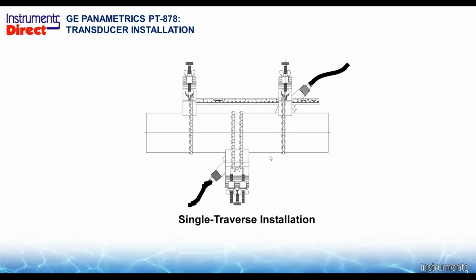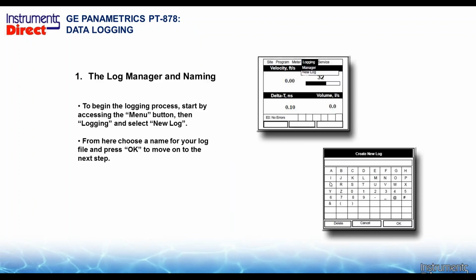You may not have to go to this plane. You need to go up and down this plane to find the sweet spot. So the single traverse is more powerful, but more difficult to do. And so you usually reserve it to larger pipe size applications. Now, the device has a logger, so if you want to leave it there for a while to collect data, I don't remember, like 100,000 data points here.